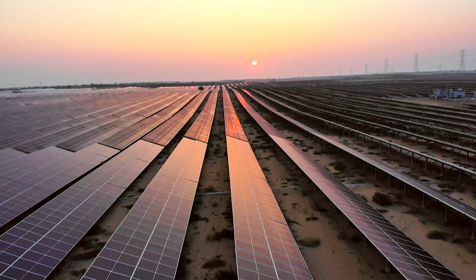To collect this power, we have made arrays. From arrays, we have made the junction boxes. From junction boxes, power is coming to the inverters. After inverter, this power is converted into AC. From there, we increase the voltage to a 33 kV system. After 33 kV system, we have connected a number of such blocks to make it a capacity of 25 megawatt.